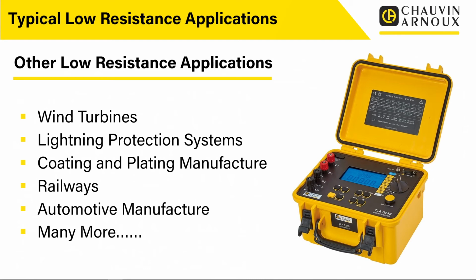Lightning protection systems in buildings. Again, we may have big copper straps coming down the outside of a building, with connections there, and they go to earth spikes and join off to different connections, and there are bolts and brackets and all sorts of stuff. Again, how do we ensure that they're correctly connected? We can use a low resistance ohmmeter to do that.